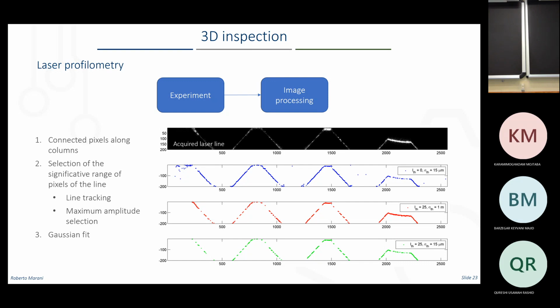And if you select your column and plot, say like this, intensity and rows, you will get 0, 0, 0, and then something that is saturated for many rows to the maximum value of intensity. So this is something that we don't want to happen, because this means that you are increasing the width of your signal, and you are adding much more inaccuracy to your measurement. It's preferable to have something with this shape, even if we don't touch 255, the maximum of the amplitude that can be detected by the camera.